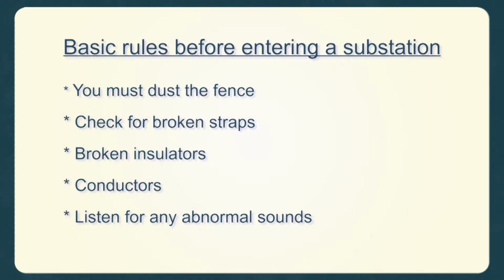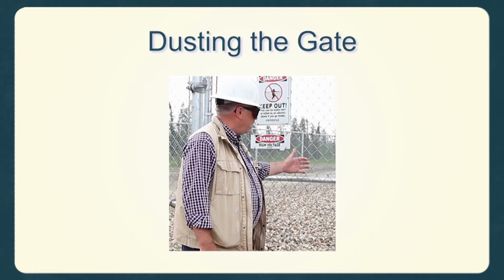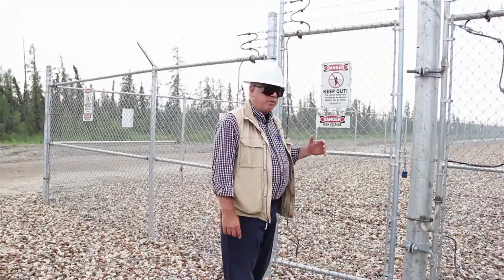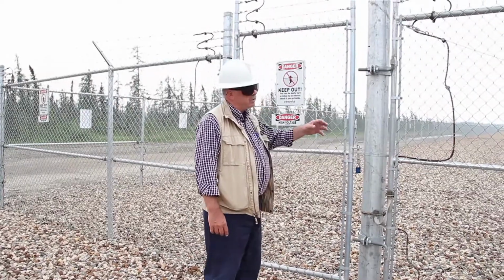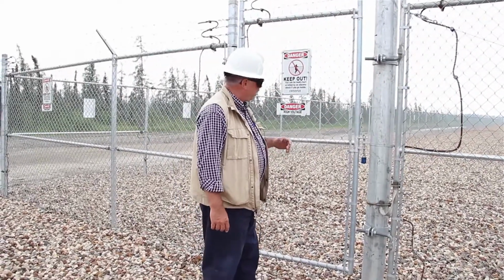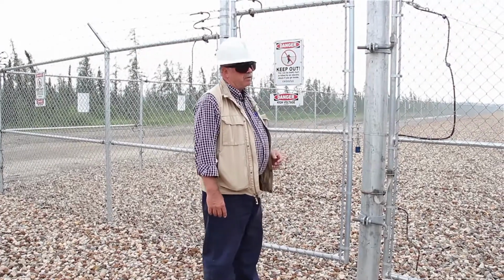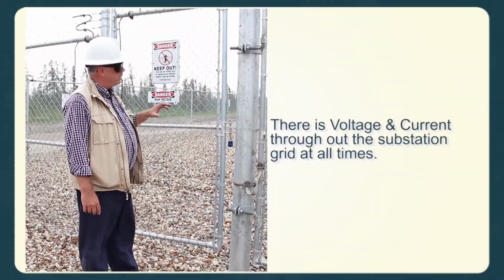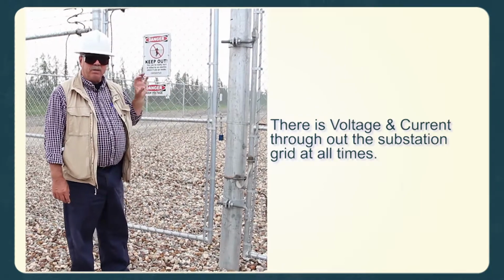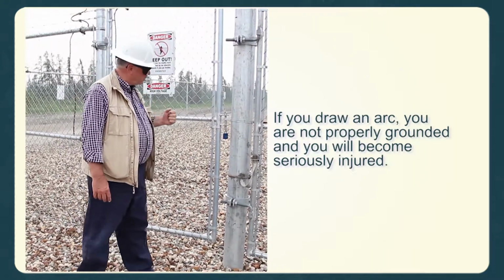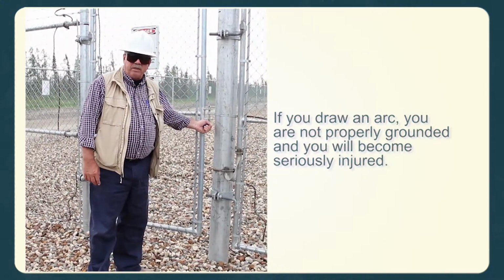Basic rules before entering a substation. You must dust the fence, check for broken straps, broken insulators, conductors, and listen for any abnormal sounds. Dusting the gate. As you're coming up to a gate to unlock it, be it a man gate like this or a big double gate like over there, get in the habit of dusting the gate with the back of your hand. The main reason for that is there's voltage and current on the substation grid at all times. If you draw an arc with the back of your hand, the last thing we want you to do is grab the lock, because then you're not leaving.